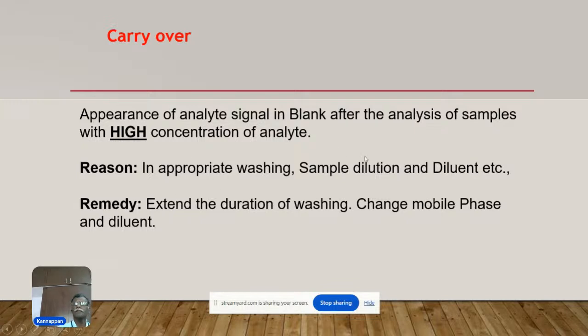Avoid it by using appropriate washing, sample dilution and diluent. So extend the duration of washing, and change the mobile phase and diluent. So that will be the remedy. The reason is actually inappropriate washing, which means we are not washing properly, along with sample dilution and diluent. If the dilution of the sample is less and more concentration is there, then it will be carried over to the next sample. So to avoid the carryover, we extend the duration of washing and change the mobile phase and also the diluent.